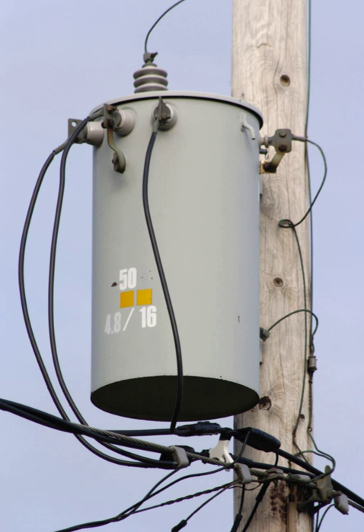Electric power distribution is the final stage in the delivery of electric power. It carries electricity from the transmission system to individual consumers. Distribution substations connect to the transmission system and lower the transmission voltage to medium voltage ranging between 2 kV and 35 kV with the use of transformers.